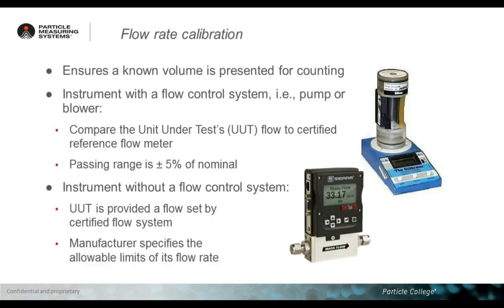So here's the explanation about each single test. The first test that is always performed on your particle counter is the flow rate calibration.